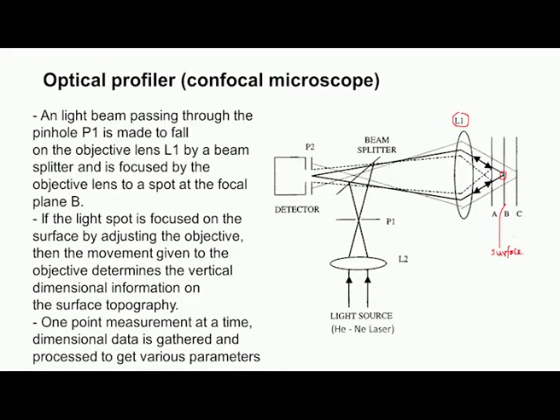If the workpiece surface is exactly at the focal point of the objective lens, then the light gets reflected, and then it will pass through the pinhole number 2, and then it will fall on the detector. If the workpiece surface is exactly at the focal point, then maximum intensity of light will fall on the detector.